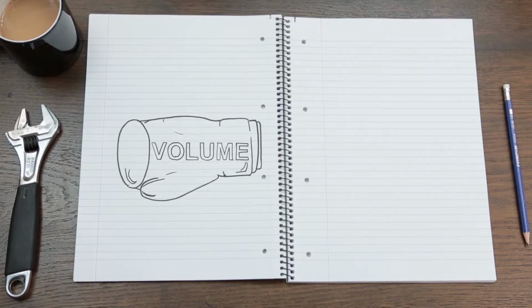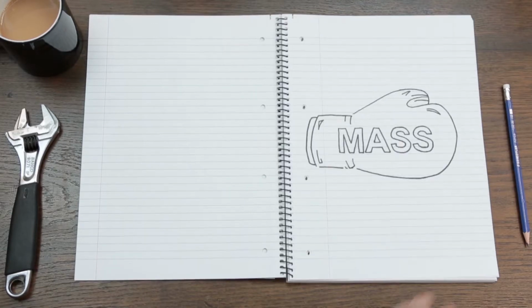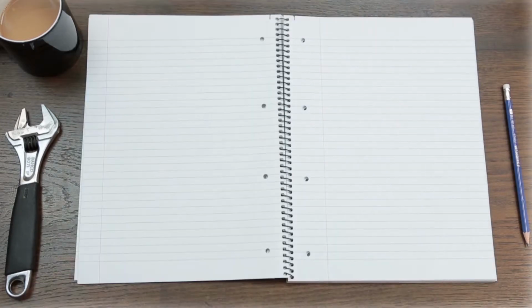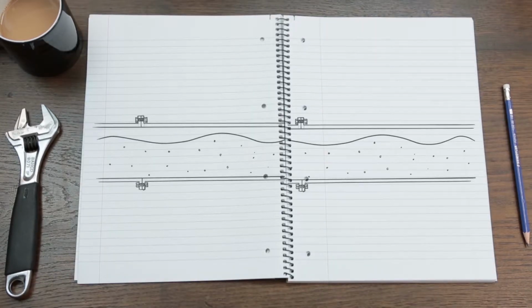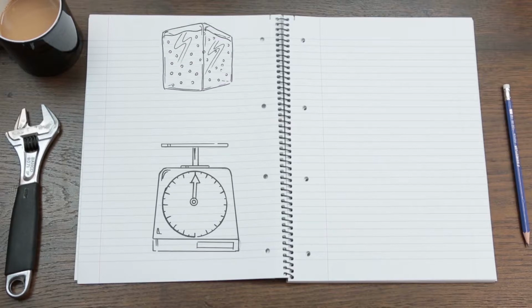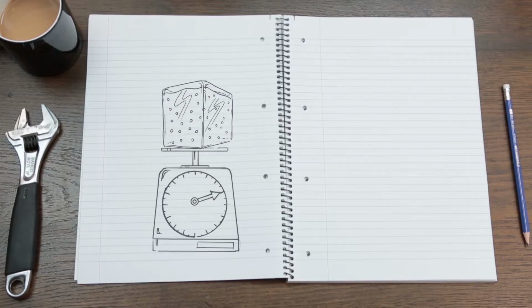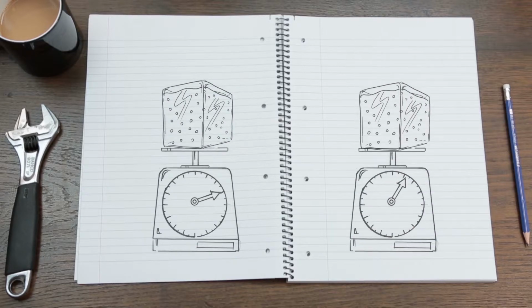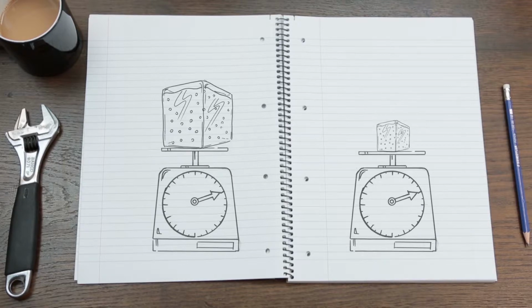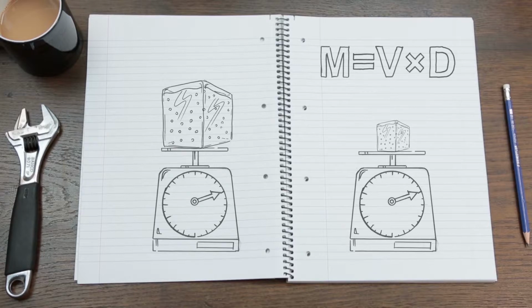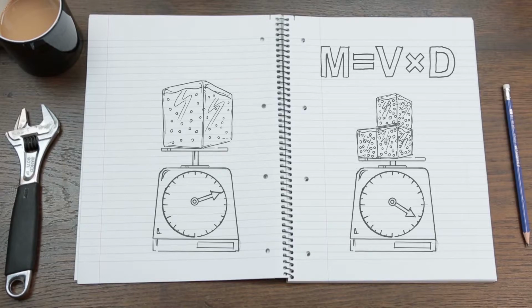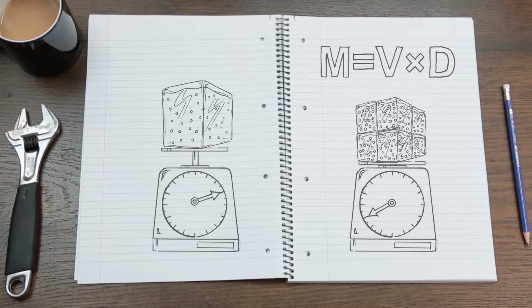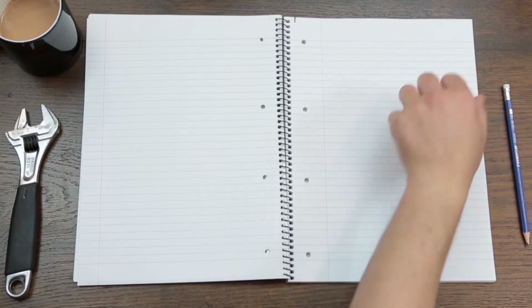Volume flow is okay if your product is sold by volume. But mass flow is simply the most accurate way of measuring the actual amount of a substance moving through a pipeline. Mass is related to volume by density. The greater the density of a substance, the larger its mass will be for the same volume. Mass equals volume times density. So simultaneous measurement of volume flow and density gives mass flow, telling us exactly how much of a substance we have.